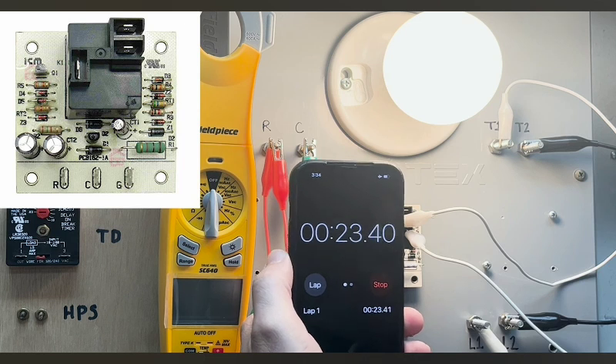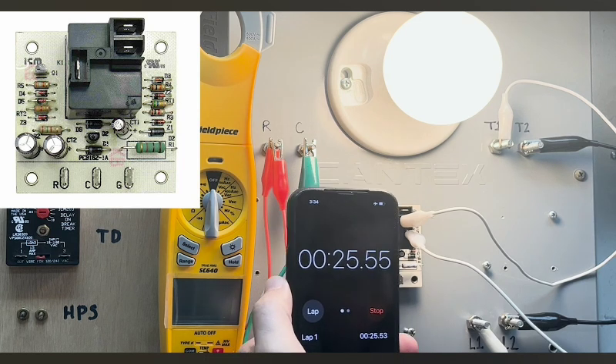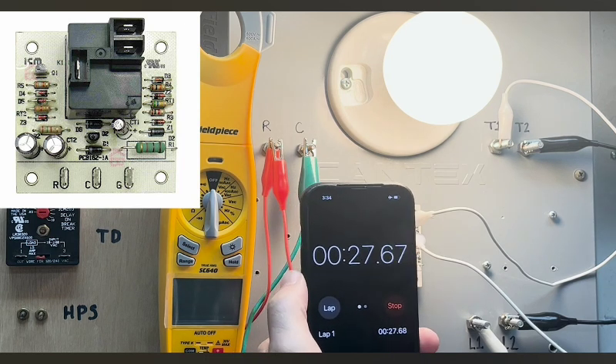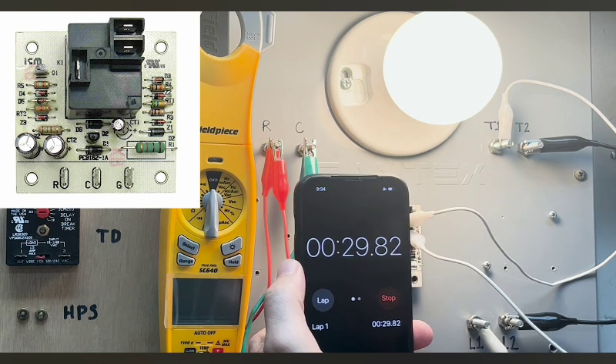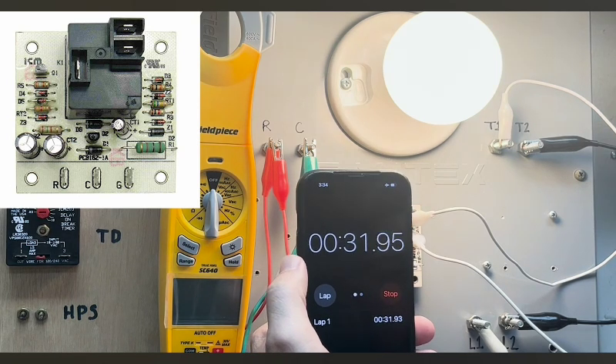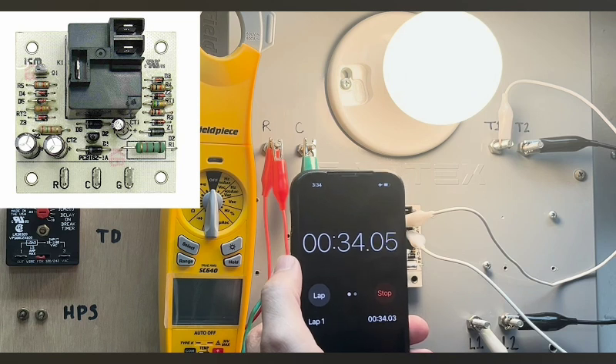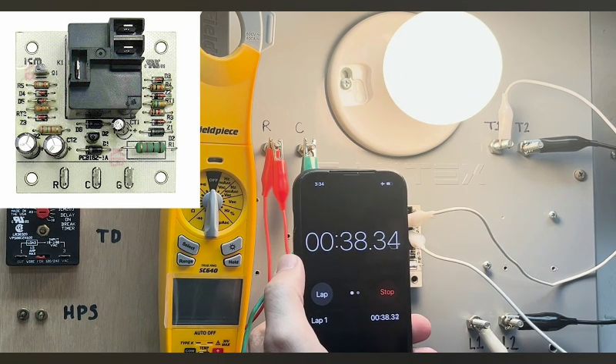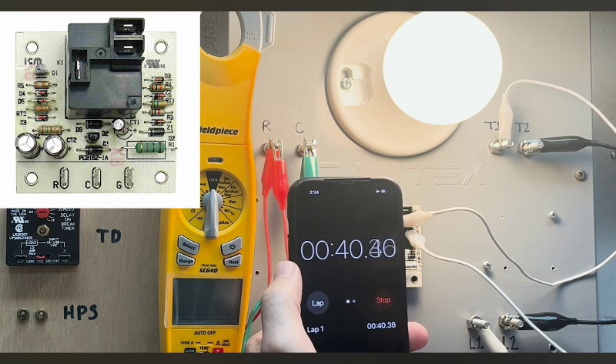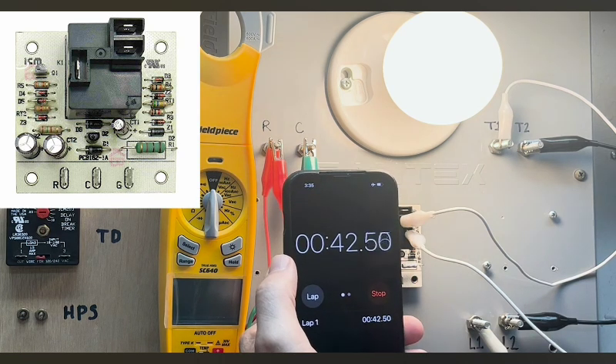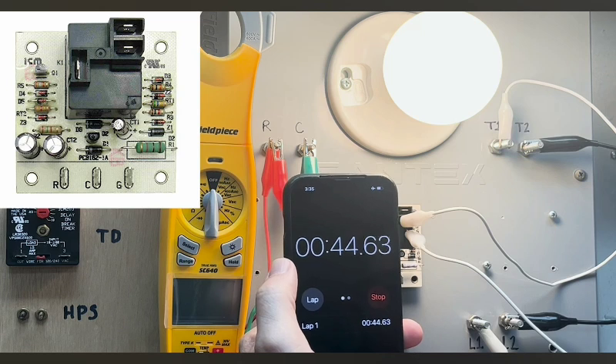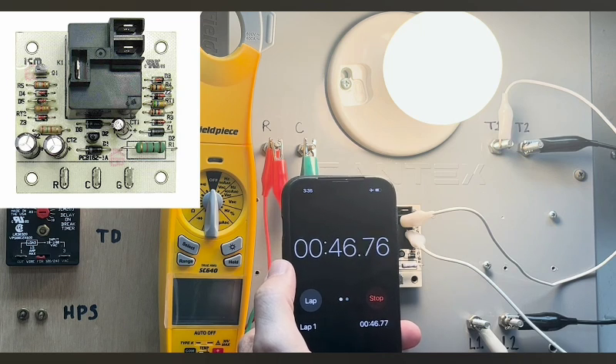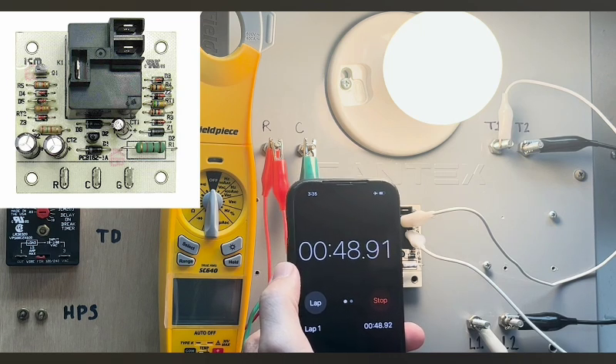And it's very important when you're diagnosing these, if you think the relay is stuck in the closed position, you want to go ahead and use your timer, because knowing that it's a 50-second off time, you want to make sure that it's not running for less than that and you're jumping the gun and saying that the board is bad. Because if you're not using a timer, 50 seconds is kind of hard to time out. Just try and imagine what 50 seconds feels like. Could feel like eternity if you're just waiting on it.